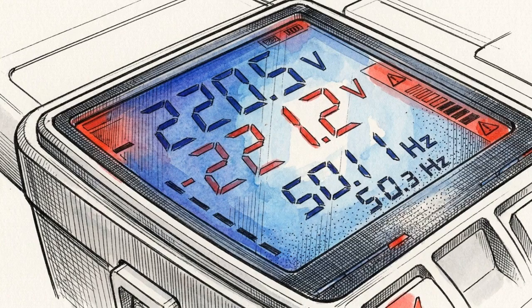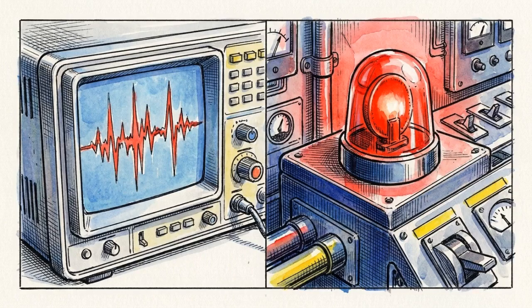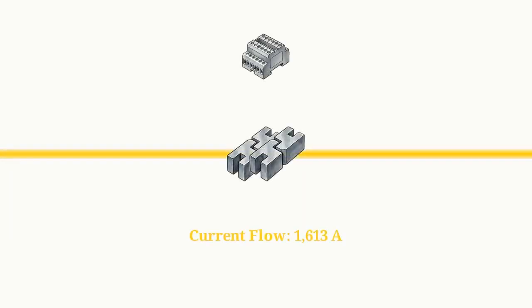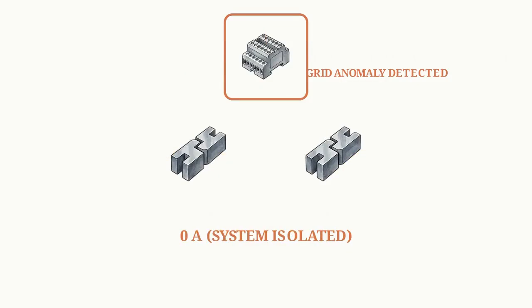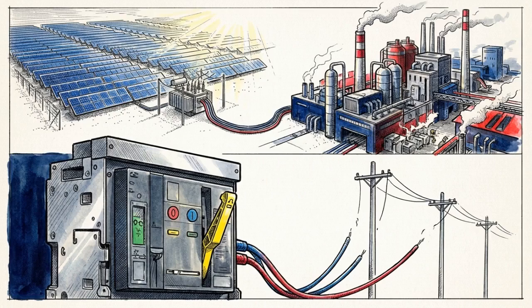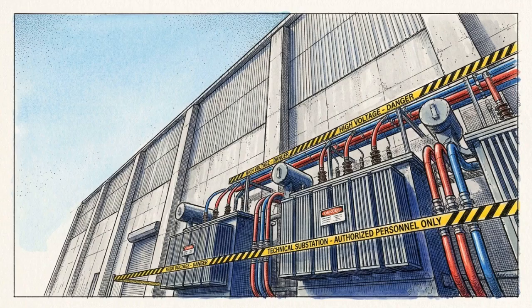These digital relays continuously scan the electrical characteristics of the municipal utility grid. If the outside utility power drops offline or fluctuates wildly, the system detects the anomaly in milliseconds. The automated response is immediate and fail-safe. The relays trigger the 2,500 ampere breaker to open, physically severing the connection. This prevents the plant from non-compliant grid islanding and stops lethal voltage from backfeeding into dead utility lines. Electrical safety at the point of connection relies on these autonomous, layered protections. They prioritize the factory's baseline grid stability over maximizing solar yield.